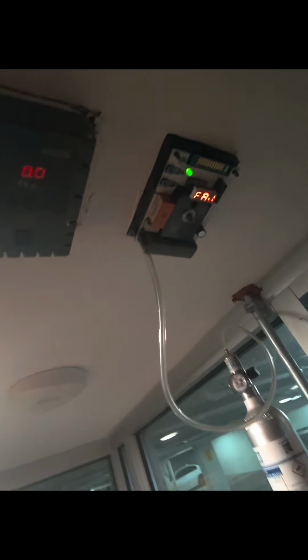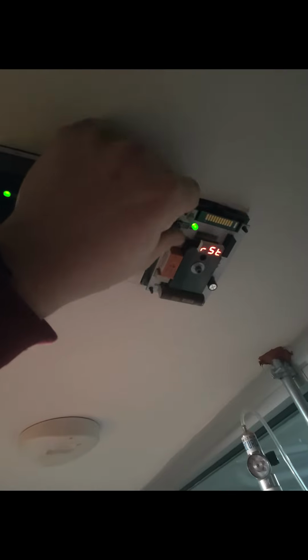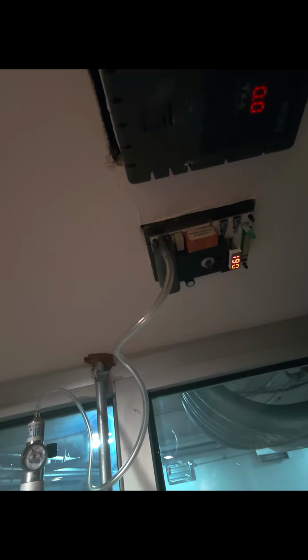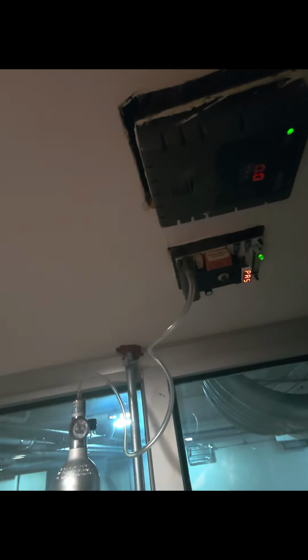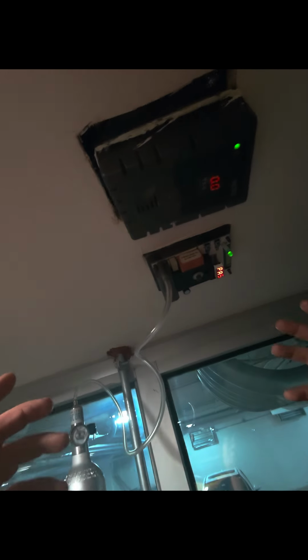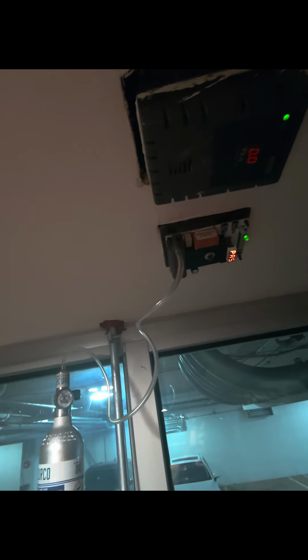All right, so we got a fail on this one. So what we're going to do is turn this gas off. Once it counts all the way down, we're going to reset the detector and then try and calibrate it again. The levels are back down to 0. We're going to go in, sensor, reset, done. All right, we got the pass this time. So that happens sometimes. Sometimes it fails the calibration the first time. If you reset the device and then calibrate it a second time, it'll pass.